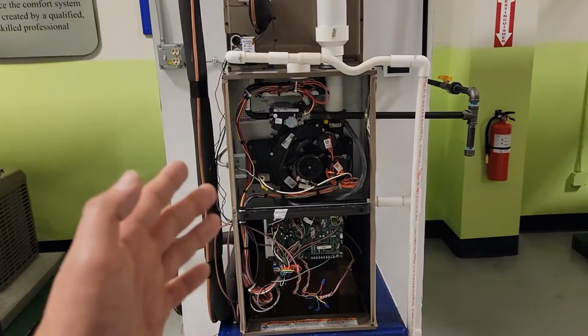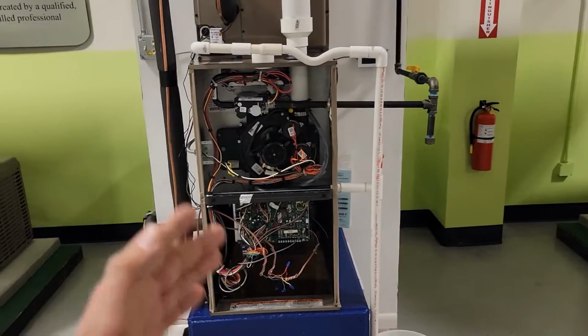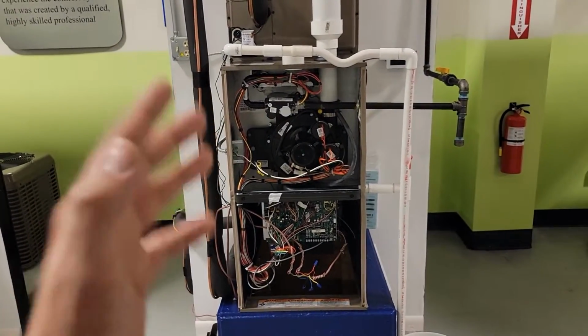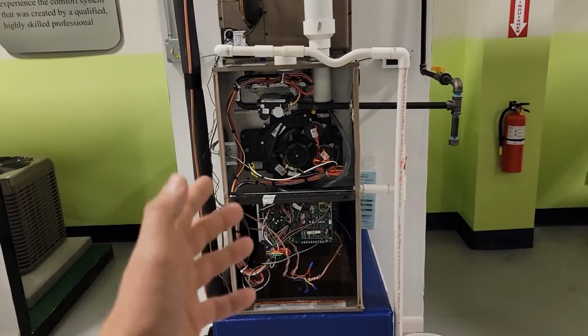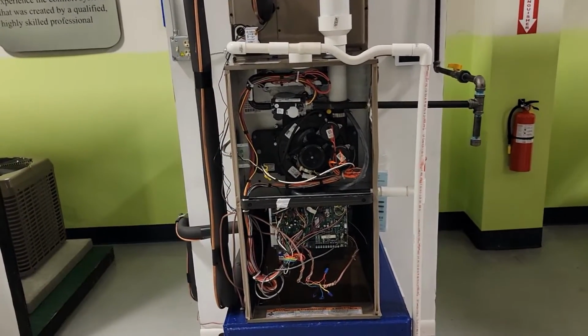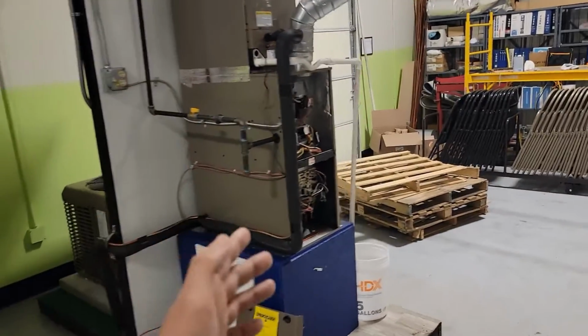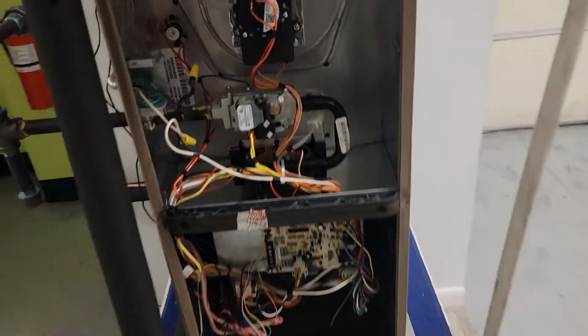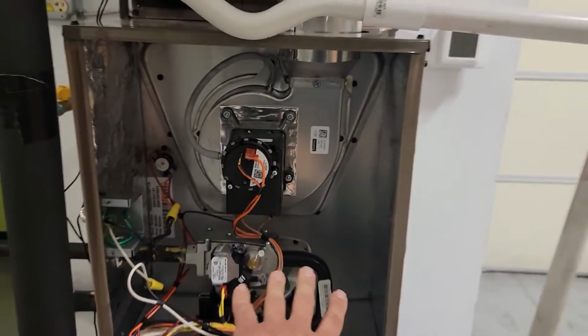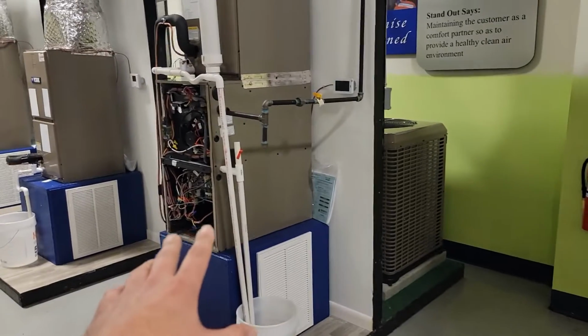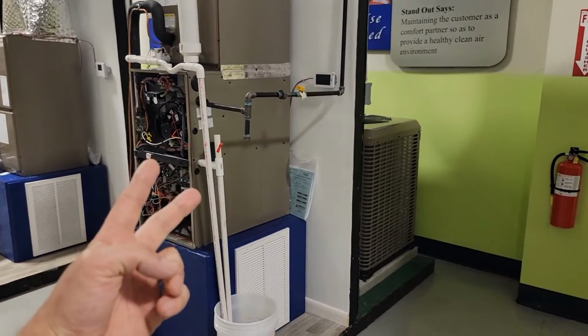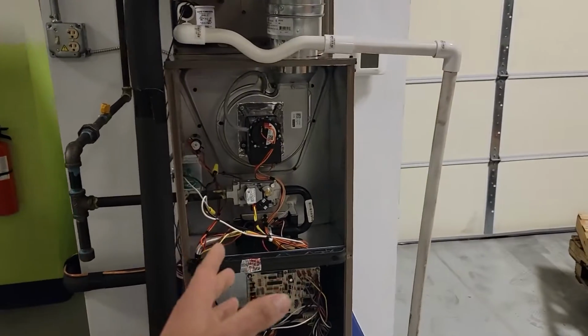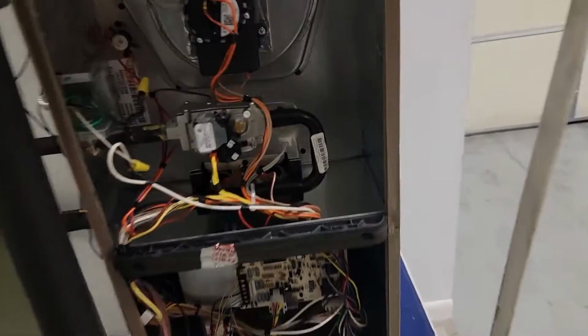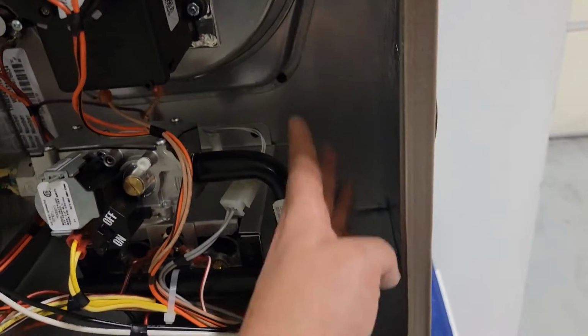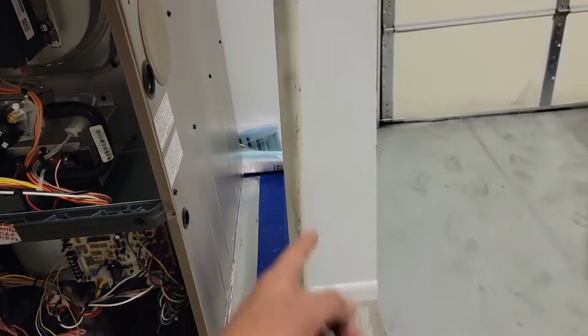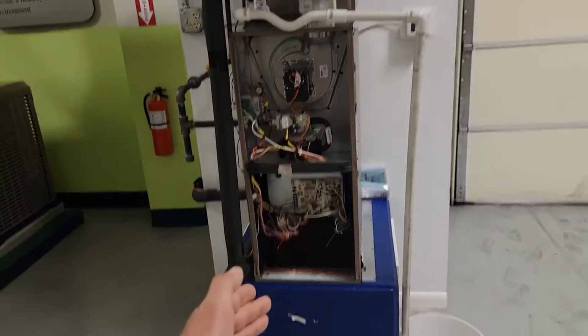And that brings me to an installation characteristic that you have to know: do not install this furnace anywhere where it gets freezing temperatures, because it could cause the drain for that condensing furnace to freeze. You don't have to worry about freezing temperatures with this 80% furnace, because it's only got one primary heat exchanger. It doesn't have a secondary heat exchanger. A condensing furnace has 2 heat exchangers, a primary and a secondary. An 80% furnace only has 1 heat exchanger. So there is no plastic collector box with a drain coming out and connecting to our drain from our coil. You can see that.